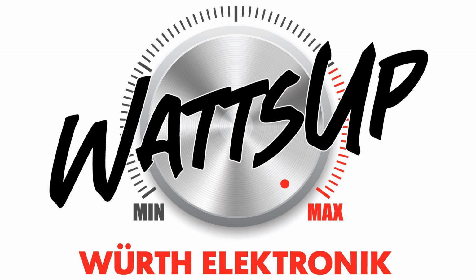And this is why we propose a new approach, which is to design your filter by looking exactly at modal measurements. So what are modal measurements? Modal measurements are common and differential mode. If you look at the 2 images that I have here, you would identify the differential mode as the noise that goes through one conductor and comes back in the other conductor in the opposite direction, while the common mode goes in the same direction for both conductors, and so it recloses through ground or through stray capacitances. So you really need to know these 2 for filter design.